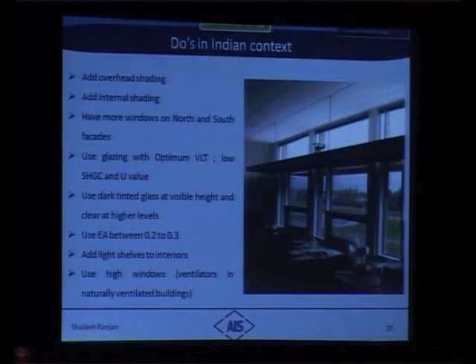So what are the do's and don'ts which we need to consider? We need to use shading, definitely. We need to do overhead shading. We need to do internal shadings. Have more windows in the north and south facade. Use glazing with optimum VLT, low solar factor and low or optimum U value. Use dark tint glass at visible height and clear at the higher level, because you are allowing the optimum light, and at the higher level where it is not the vision area, it will penetrate the light much inside the building. So these are the do's.